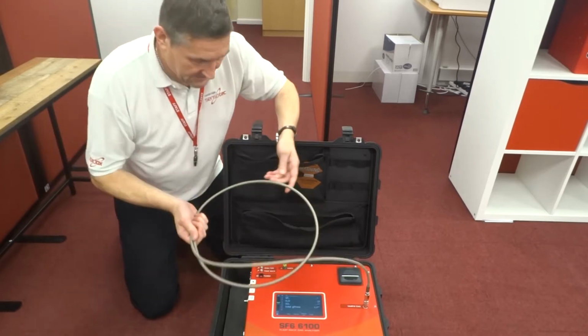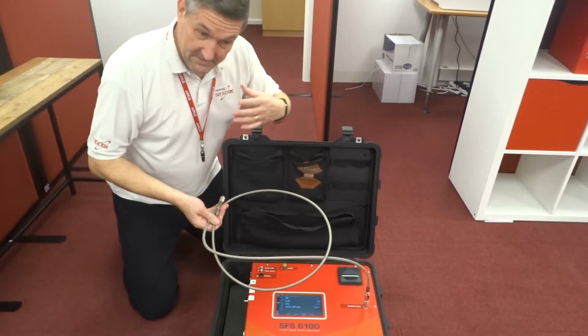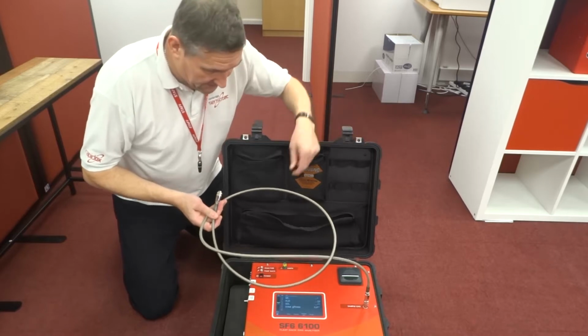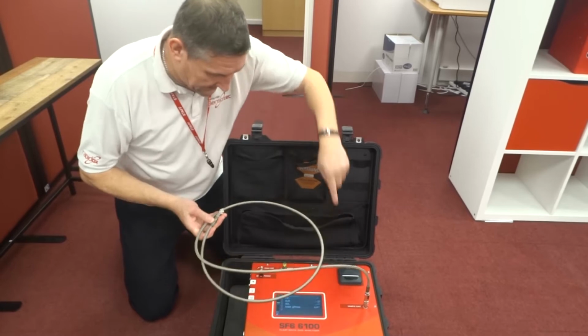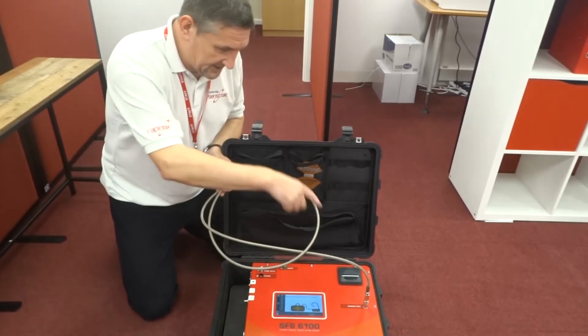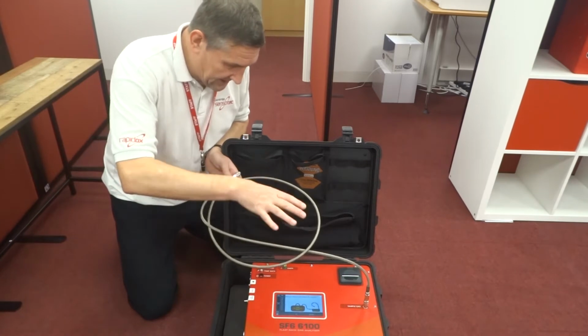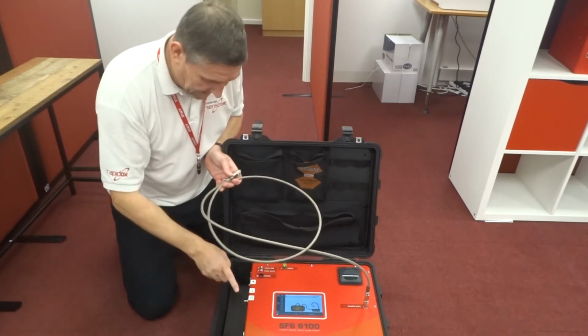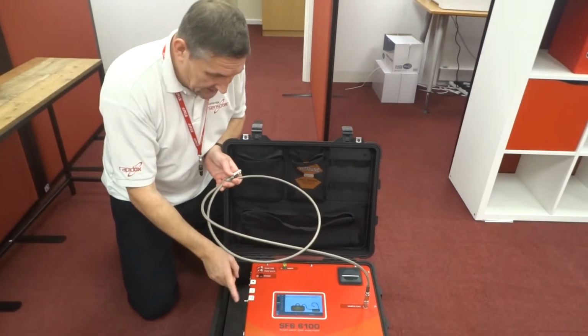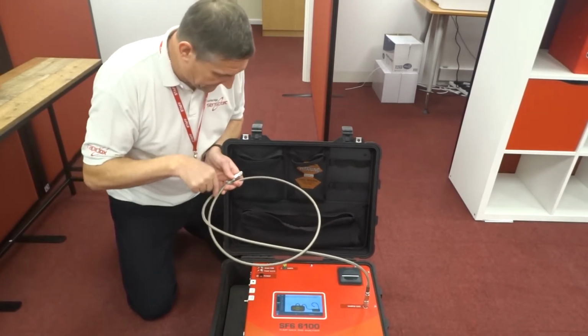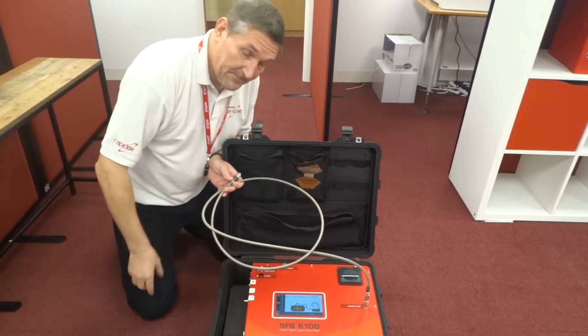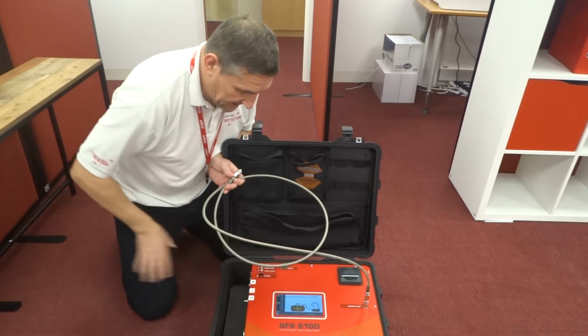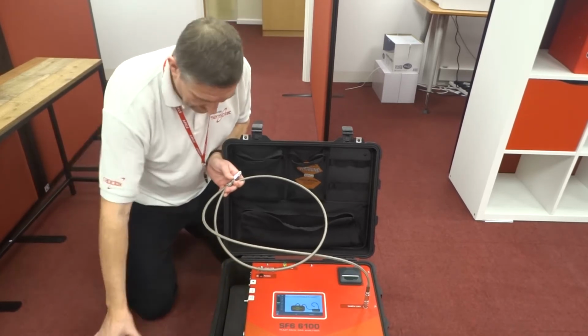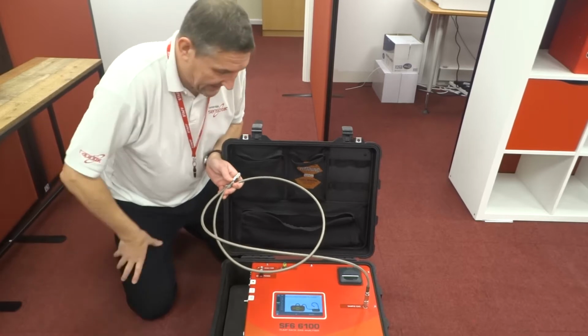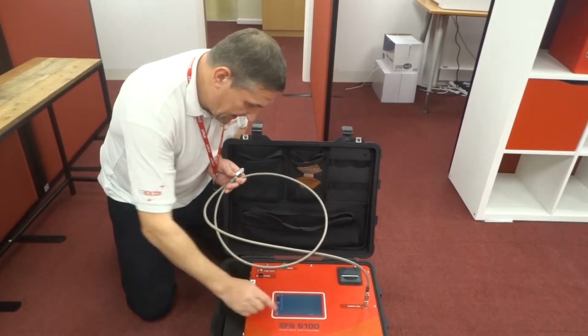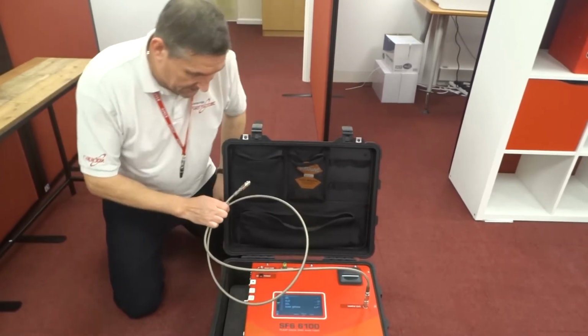Now this hose here is full of gas and it might be contaminated gas, so when you start your measurement you should always do a line purge, and we press the line purge button. If this hose has got some gas in it, the analyzer will vacuum out the gas and dump it out of this bypass port. So if you absolutely need to collect the very small amount of gas that is inside this hose, then you will need to attach a gas recovery bag to this point here, and the gas will then be ejected into your bag. I'm going to press OK, and the line purge will start.